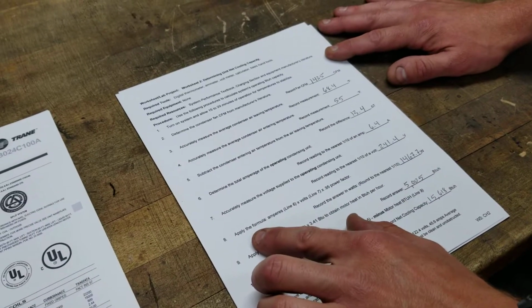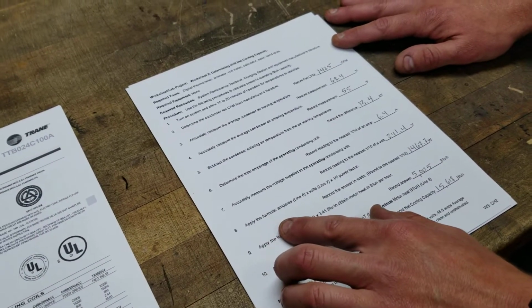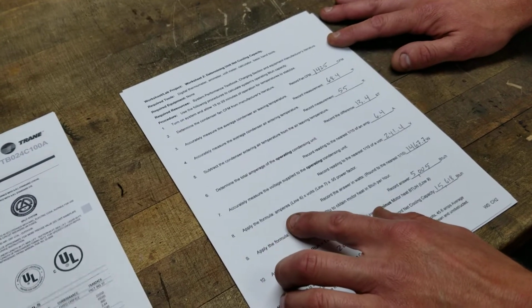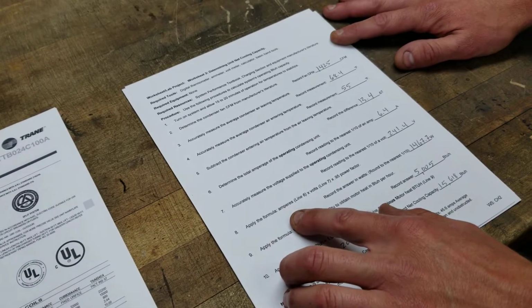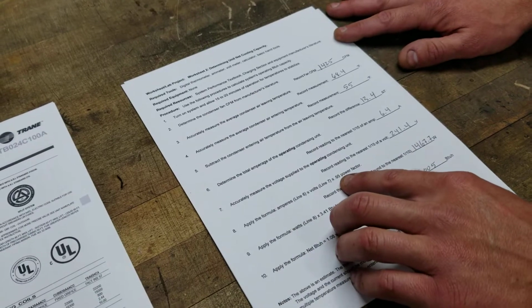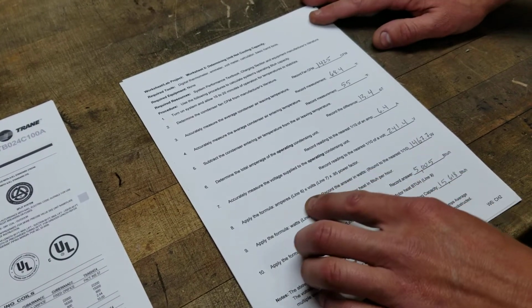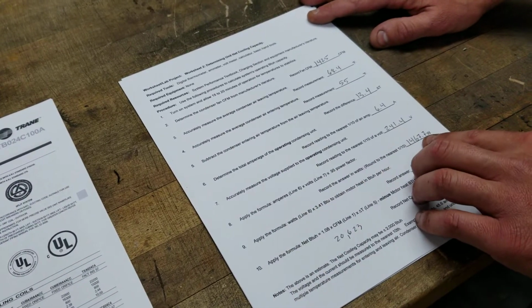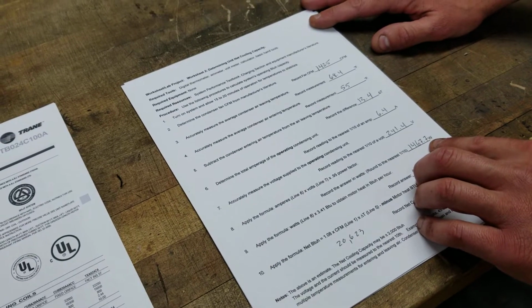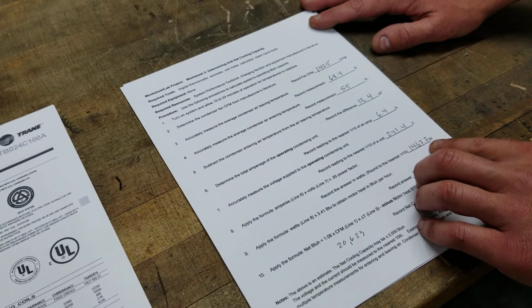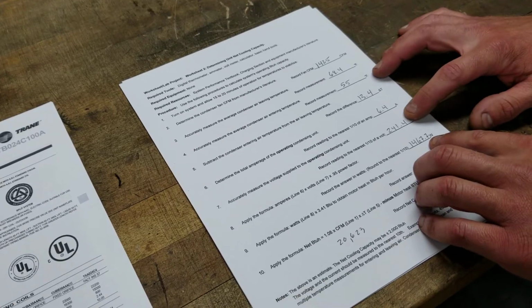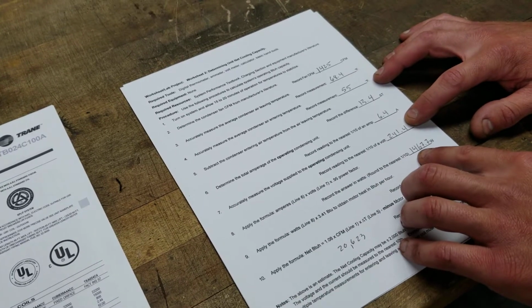And then we just got a little bit of math, and this worksheet breaks it down for us. So our amps times volts times our power factor, we just use .95 as a constant. I came up with 1467.7 watts. Okay, and all that is amps times volts times the power factor. We got our watts.